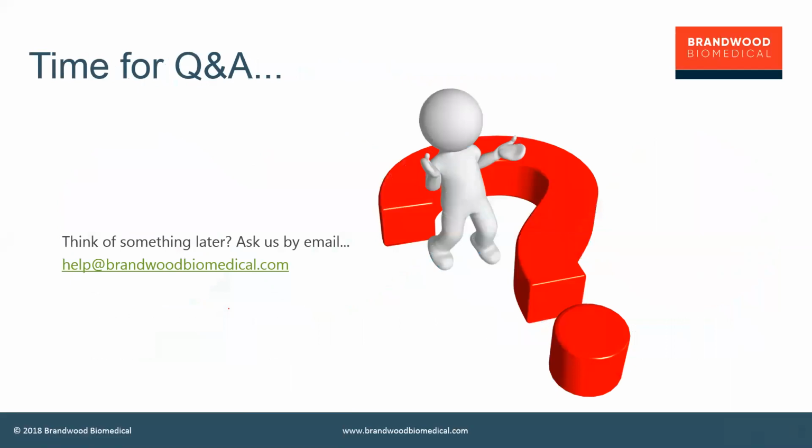In other words, I don't have any international regulatory certifications. I just want to come straight here into Australia. I've got something very new. Well, Tracy, the answer to that is that if you're going to do that, you're going to need to come directly to TGA and go for a direct TGA conformity assessment.